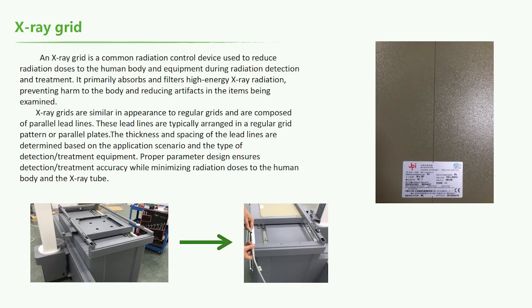The next one is a common radiation control device. It is called the X-ray grid. It is used to reduce radiation doses to the human body and equipment during radiation detection and treatment. It primarily absorbs and filters high-energy X-ray radiation, preventing harm to the body and reducing artifacts in the items being examined.